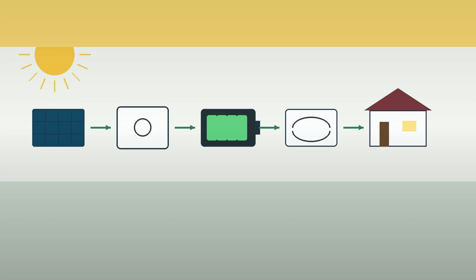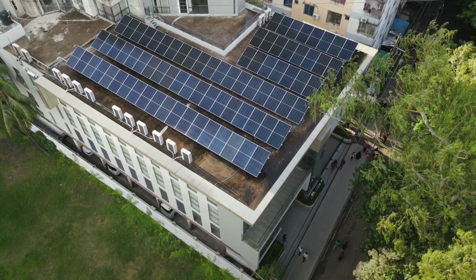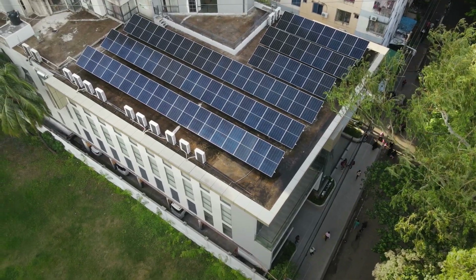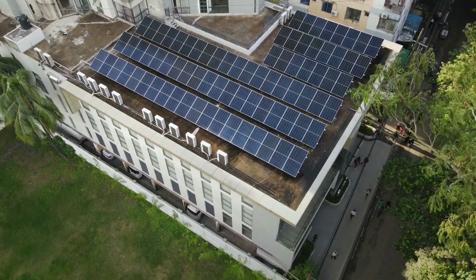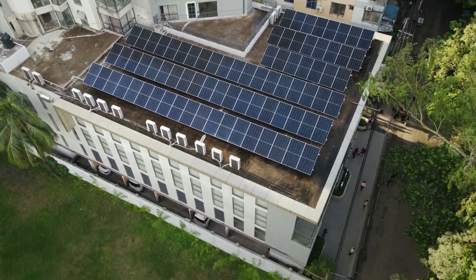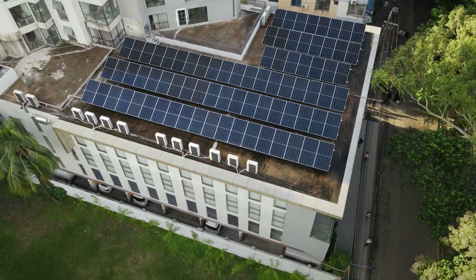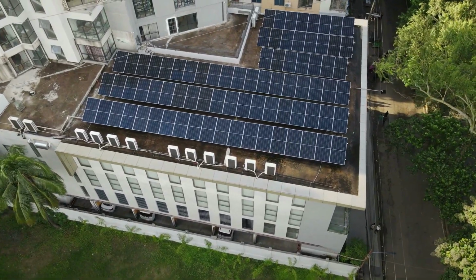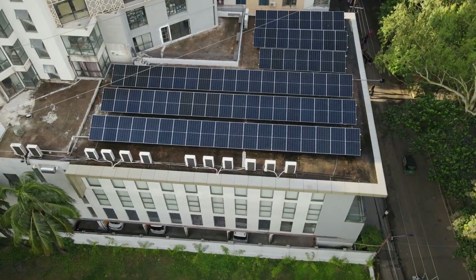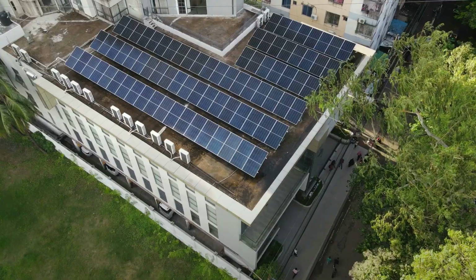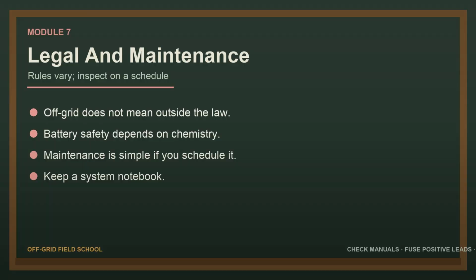Battery sizing is daily watt-hours divided by system voltage. At 12 volts, 1,200 watt-hours is about 100 amp-hours before depth of discharge headroom. With LiFePO4, you can commonly use more of the capacity than lead acid, but you still want reserve. A 2,000 watt-hour daily cabin might start around 200 amp-hours at 12 volts, or 100 amp-hours at 24 volts, then grow for cloudy day autonomy.